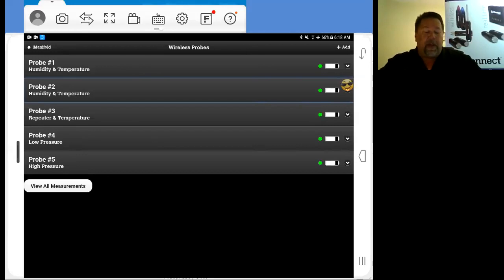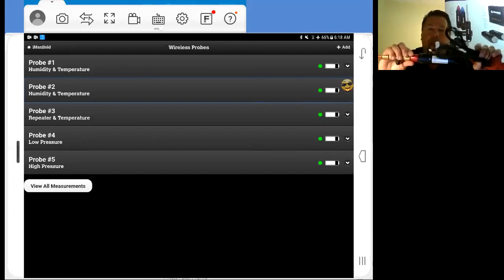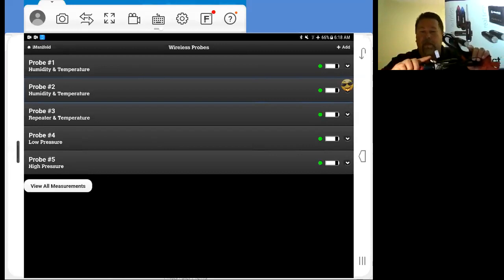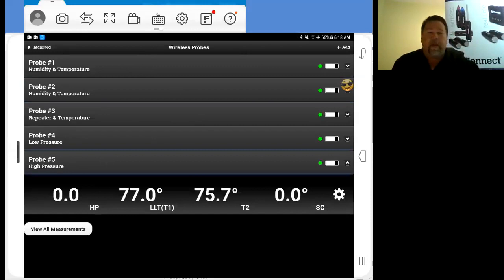Good. So right now on my high side here, I've got my liquid line temp on T1, my discharge line temp on T2. Now we're going to go ahead and open up this probe. We're going to go to the high pressure probe and open this up. As you can see, we have no pressures on here. I'm not hooking this up live. We've got our liquid line temp shown. That's automatically mapped. Our T2 here that I'm using for my discharge line temperature, I just need to map that.